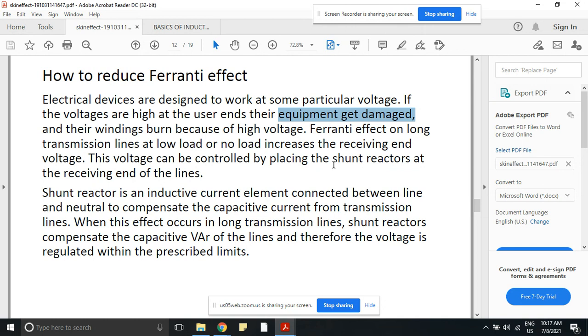So already you are having the effect of shunt capacitor. So to nullify that effect of shunt capacitor, what we have to do? We have to place shunt reactors at the receiving end of the lines. So then the shunt reactor will balance the charging currents taken by the capacitor. Hence, the receiving end voltage will remain unaffected as before in case of short transmission lines, and it will be less than your sending end voltage. So our purpose is always to maintain Vs is equal to Vr. Vr should not be greater than Vs.